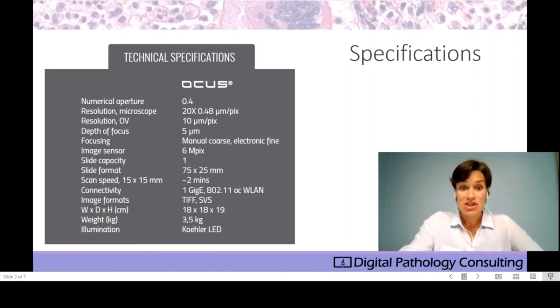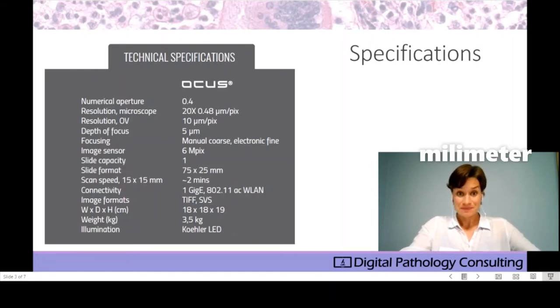The specifications: things that are very important for me is that the resolution is 0.48 micrometers per pixel, which is comparable to what other high throughput or multi-slide scanners are doing with the 20x objective. And it takes around 2 minutes to scan a 15x15 millimeter specimen. And you can have different image formats: TIFF, Pyramid TIFF, or an SVS file. And it just weighs 3.5 kilos. It's small, 3.5 kilos, that's less than 8 pounds. And 18 times 18 times 19 centimeters, less than 8 inches. So you saw how small it was.